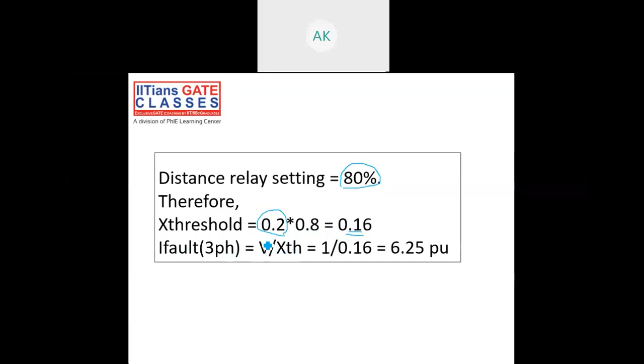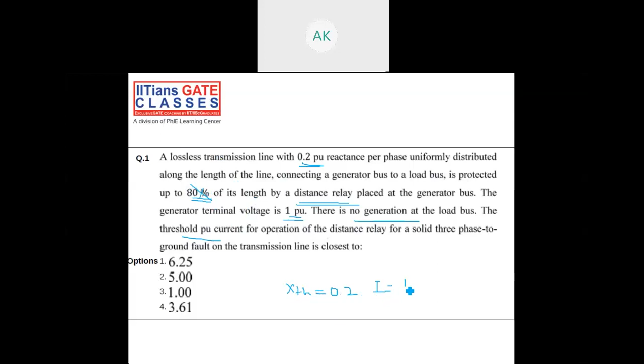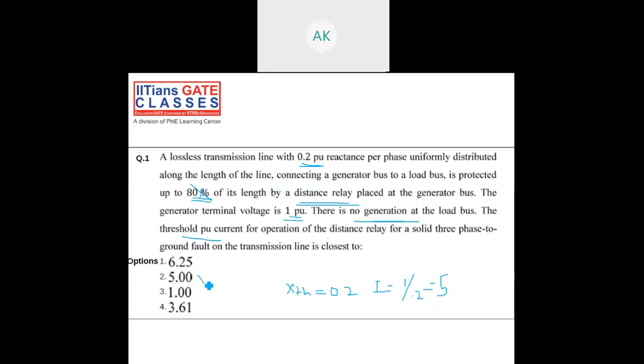Okay, let's look at it. So the distance relay setting is 80%, right? And so the X threshold is actually 80% of the actual impedance. That is 0.2 into 0.8 will be 0.16, and the fault current will be V by X, which is 6.25. Right? Suppose in this question you forgot or ignored the fact that the setting is 80%, then you will take the XTH as 0.2 and you will calculate the current as 1 by 0.2, and there is an option for it, right? You have to be careful, right?